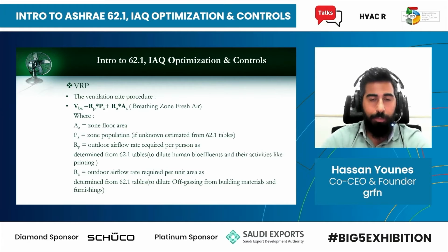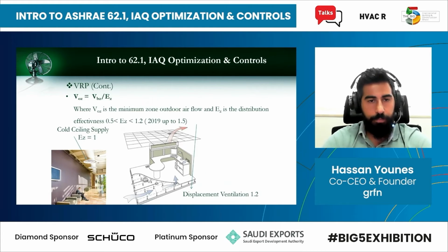So this is the equation that was introduced in 2004. And as you can see, V sub BZ is equal to the rate per person times the population, the number of people, plus the rate per area times the area. This can be taken from the tables. Based on the type of occupancy, you go to the table and find out these numbers, plug them in, and get the required volume of outside air that should reach the breathing zone.